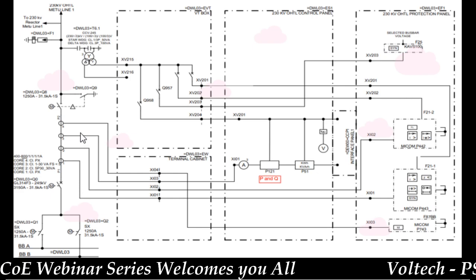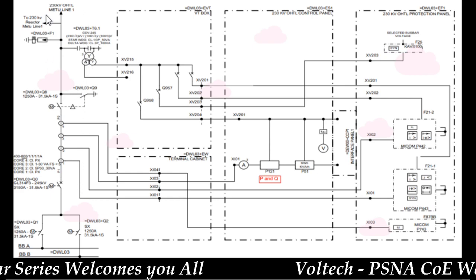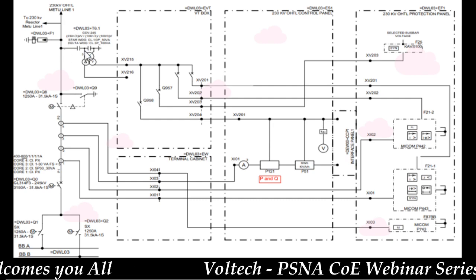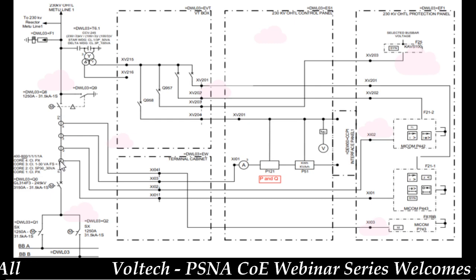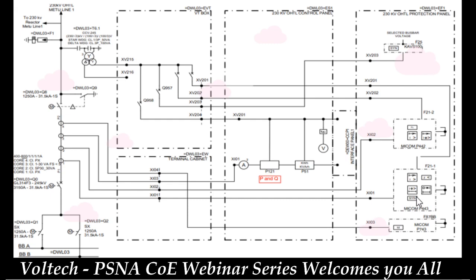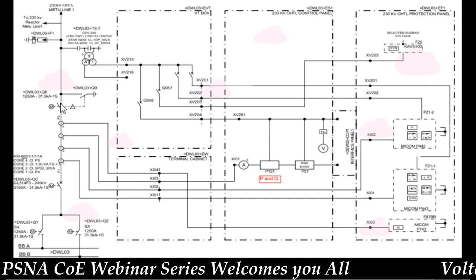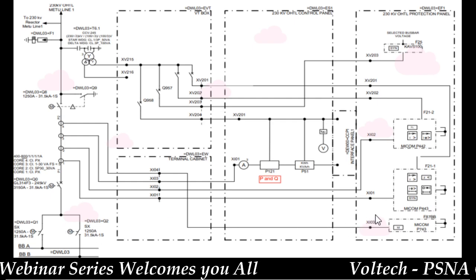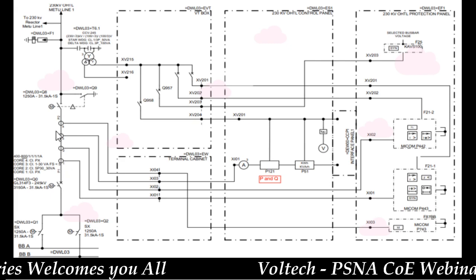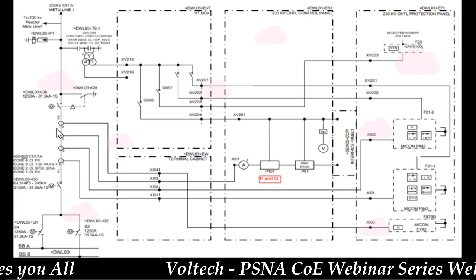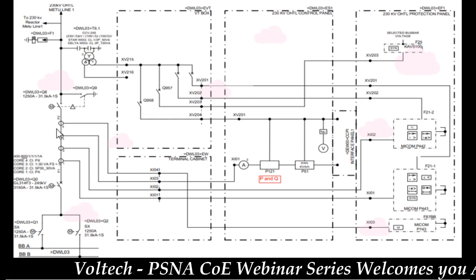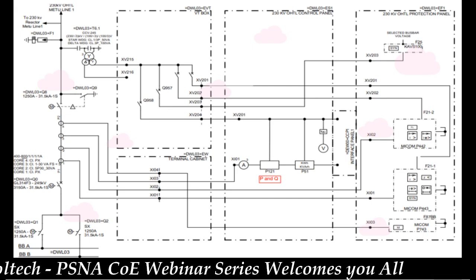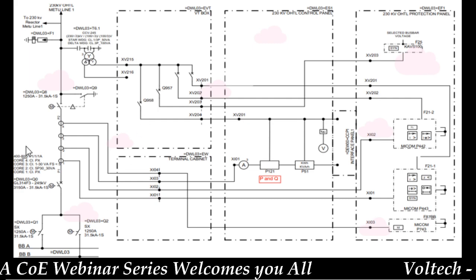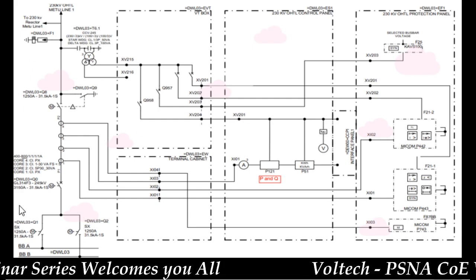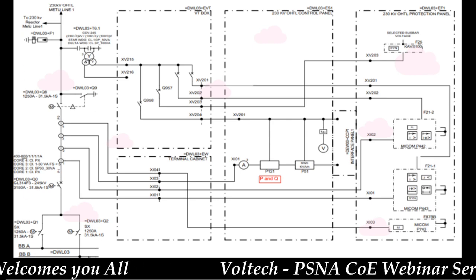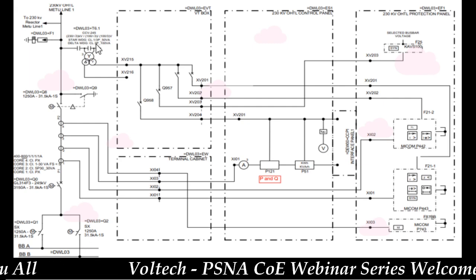Now we are going to talk about the secondary things. These are the primary. So the primary is giving the secondary information. So CT is connected to the protection relays. VT is also connected to the protection relays, and the breakers, disconnectors, everything is connected to the monitoring and control devices. So here it's a simple construction mentioning what are the analog inputs given to the relays, and what are the protection relays available in the system. This is called one bay. Bay means a space specially given for this particular line. Bay means a defined space for this line.